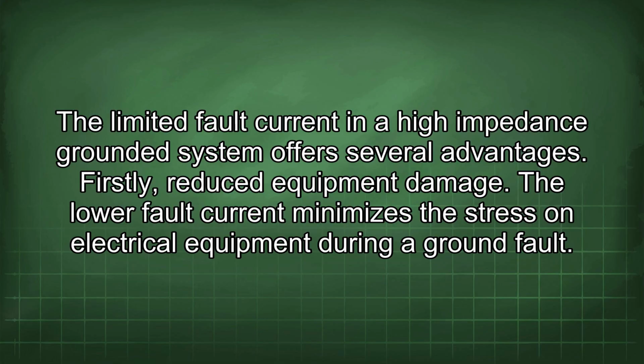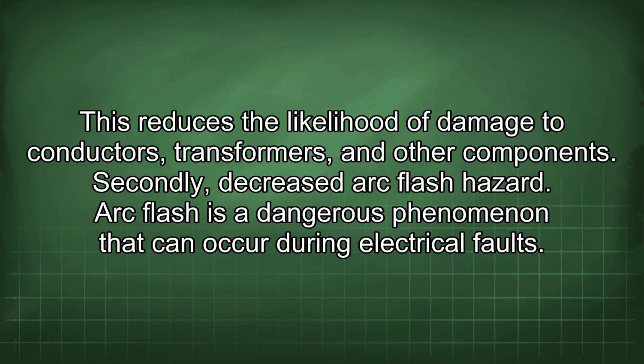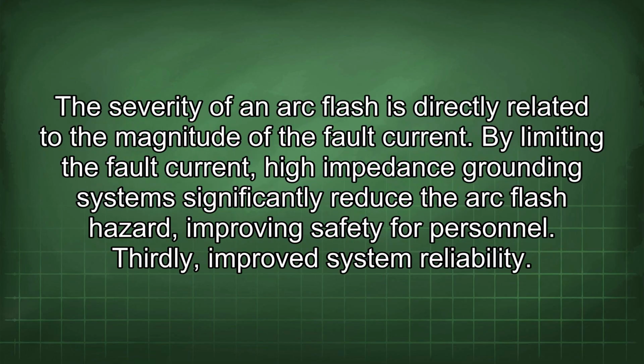Firstly, reduced equipment damage. The lower fault current minimizes the stress on electrical equipment during a ground fault. This reduces the likelihood of damage to conductors, transformers, and other components. Secondly, decreased arc flash hazard. Arc flash is a dangerous phenomenon that can occur during electrical faults. The severity of an arc flash is directly related to the magnitude of the fault current. By limiting the fault current, high-impedance grounding systems significantly reduce the arc flash hazard, improving safety for personnel.